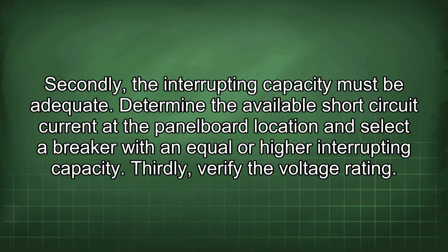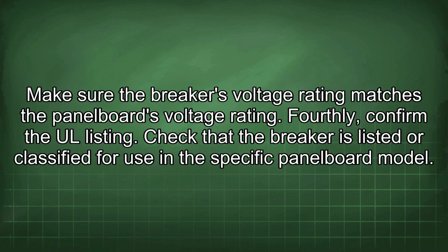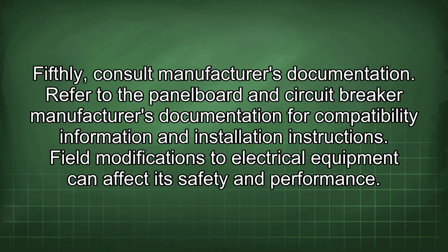Secondly, the interrupting capacity must be adequate. Determine the available short circuit current at the panelboard location and select a breaker with an equal or higher interrupting capacity. Thirdly, verify the voltage rating. Make sure the breaker's voltage rating matches the panelboard's voltage rating. Fourthly, confirm the UL listing. Check that the breaker is listed or classified for use in the specific panelboard model. Fifthly, consult manufacturer's documentation. Refer to the panelboard and circuit breaker manufacturer's documentation for compatibility information and installation instructions.